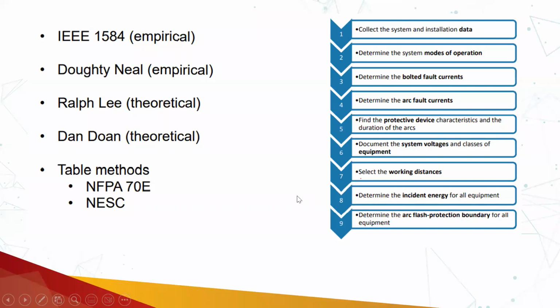So the last step is about the incident energy, and the final step is about the arc flash boundary calculation. We will be inputting the working distance ourselves, whether at that particular location the working distance will be 18 inches, 24, 36 inches. Based on that working distance, we will be determining the incident energy for all the equipment as well as the arc flash boundary for that particular equipment.